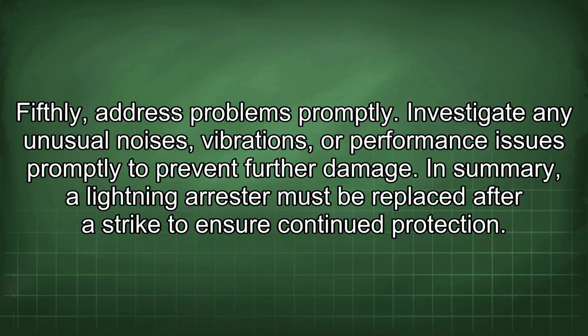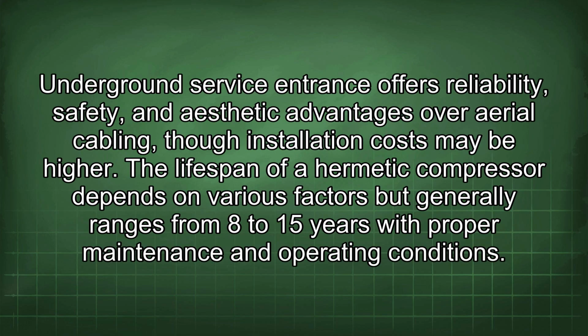In summary, a lightning arrestor must be replaced after a strike to ensure continued protection. Underground service entrance offers reliability, safety, and aesthetic advantages over aerial cabling, though installation costs may be higher. The lifespan of a hermetic compressor depends on various factors but generally ranges from 8 to 15 years with proper maintenance and operating conditions.